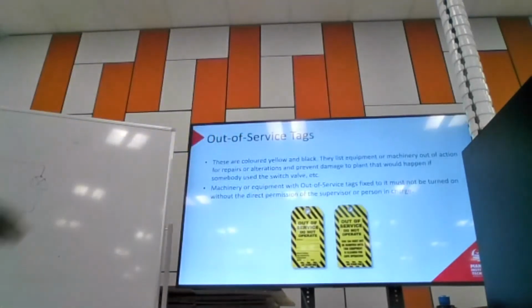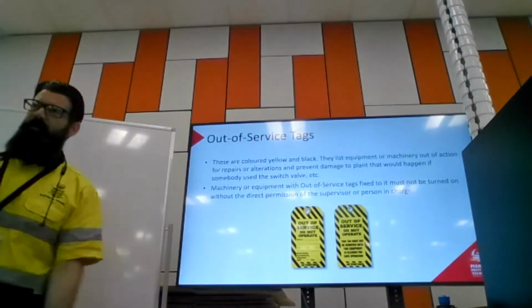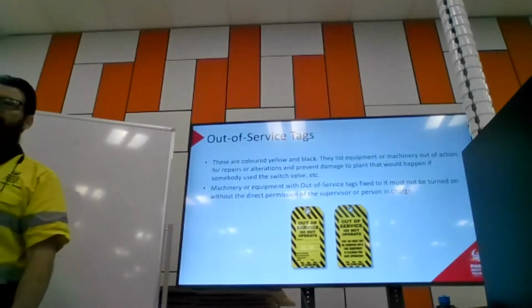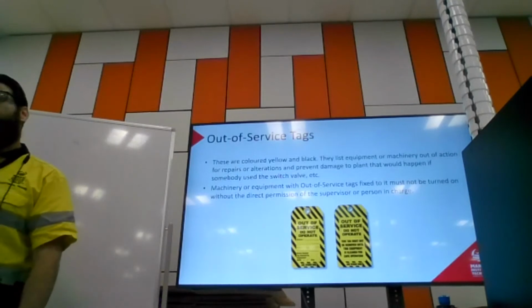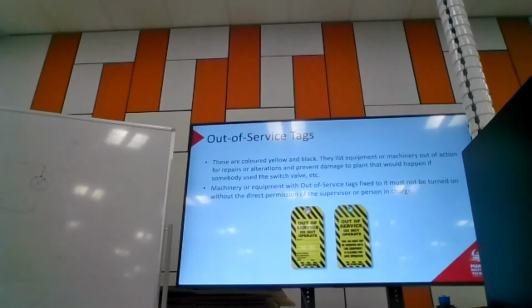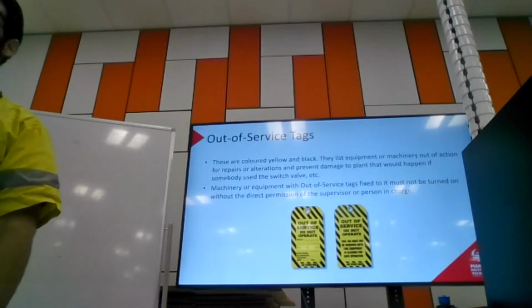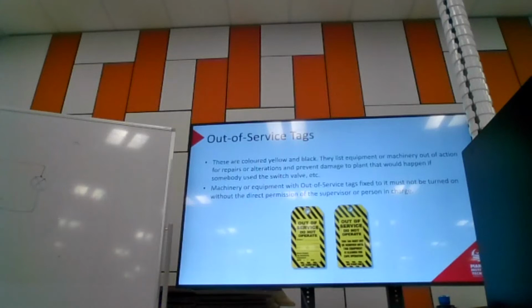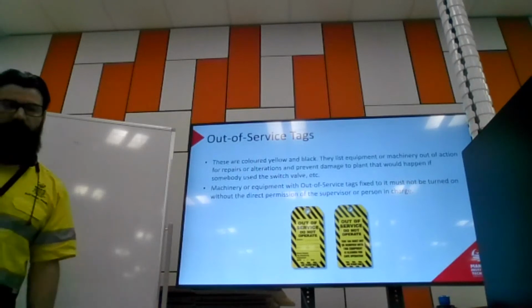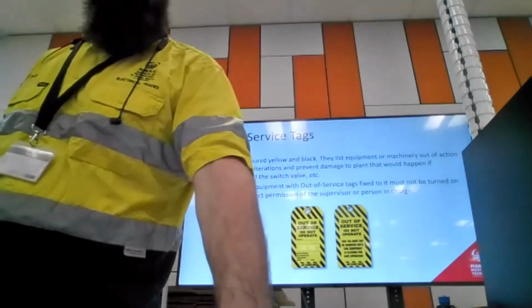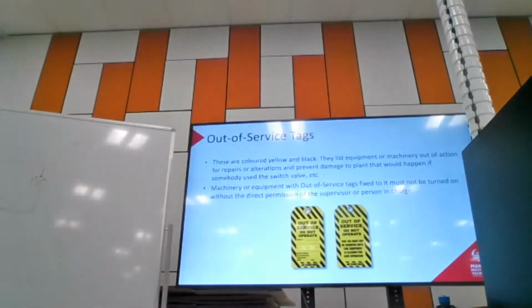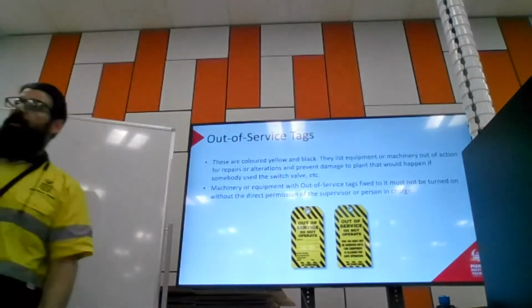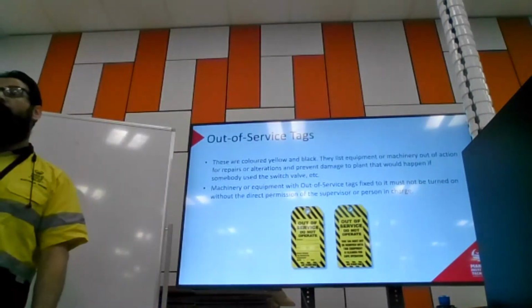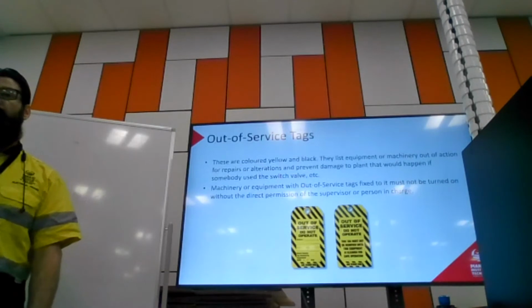This is what our out of service tags look like. I don't think I've really used one, to be honest. Mainly for me it's always been, as long as there's some sort of tag on there, that's what the law says. All that section 106 of the regulations says is that you must attach a suitable tag. It doesn't say it has to be a danger tag for this or an out of service tag for that. It'd be nice if everyone followed it the same way, but worst case, if you just attach a danger tag all the time, that's what it is, as long as it's got a tag saying don't use it. But technically, the way we use these: a danger tag is for something I'm working on right now. An out of service tag is something I've worked on, I'm not currently working on it, but I still don't want anyone to switch it back on.